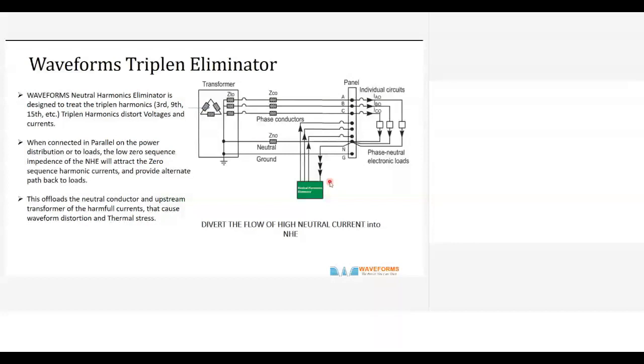I just explained this in residential places especially. You have loads that have third harmonic. Take your washing machine, which is a drive-driven machine. You have a single phase drive, which will have a lot of third harmonic. In fact, I've tested a washing machine and found 20 to 30% third harmonic current, even 40%. And some LEDs are very poor drivers, so they can generate a lot of third harmonic.